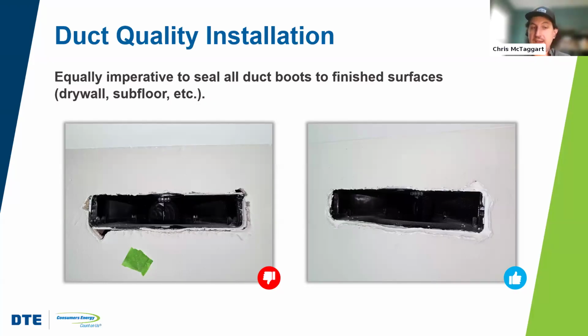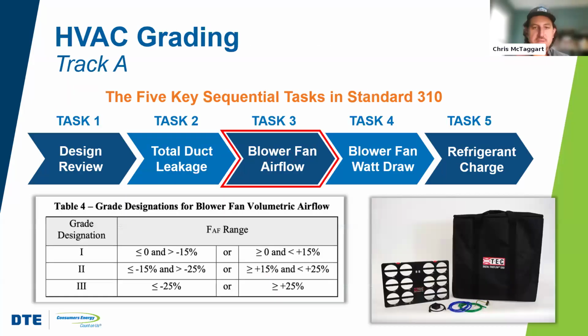So you actually do have to seal those connections. This is the number one failure within Energy Star, not sealing boots to the finished surface. So don't forget about it. If you're working with a new builder, a new HVAC contractor, you really have to drill home the importance of this.